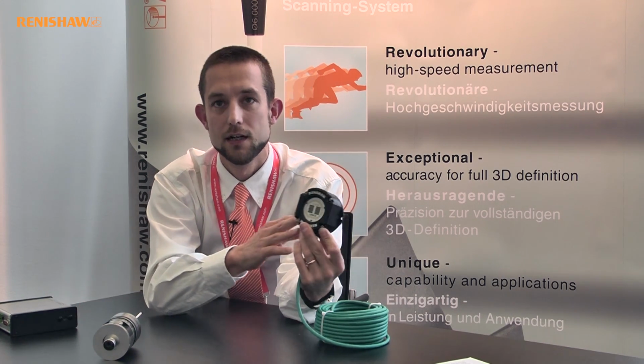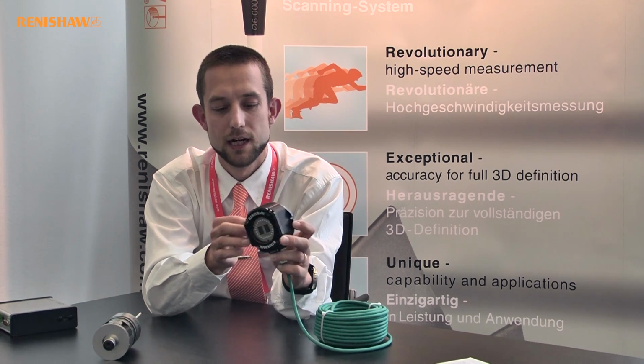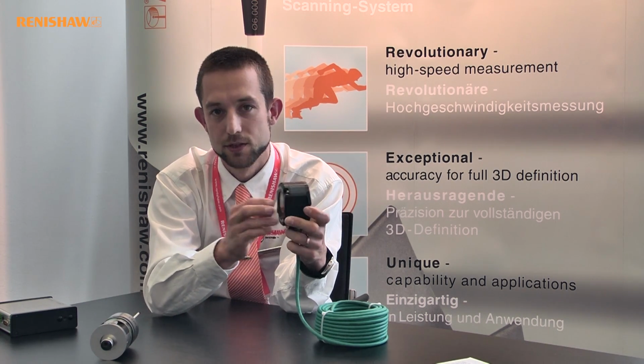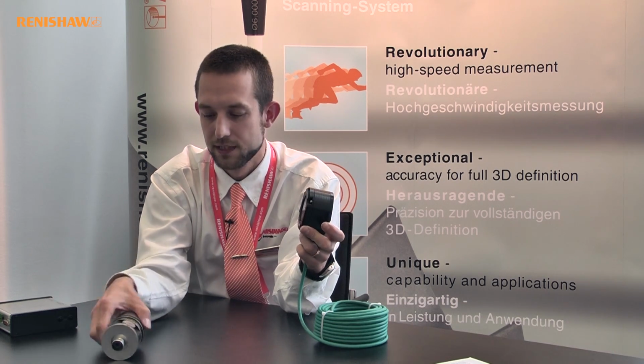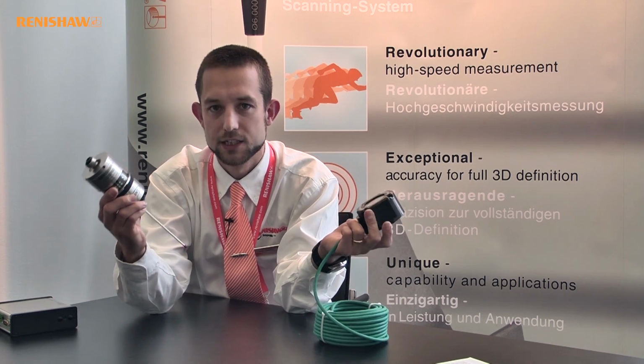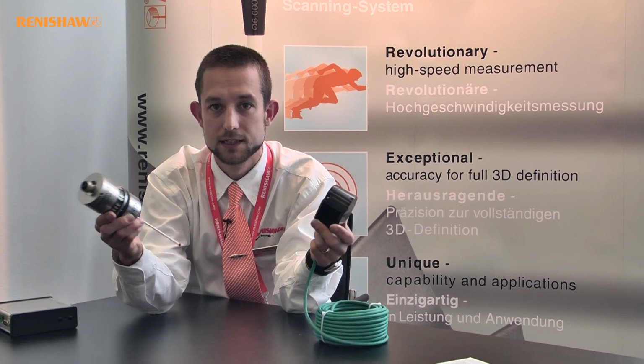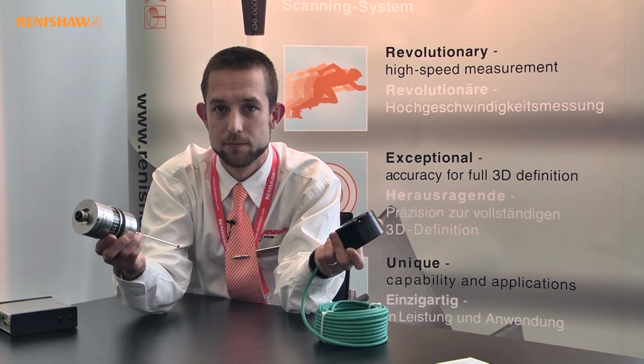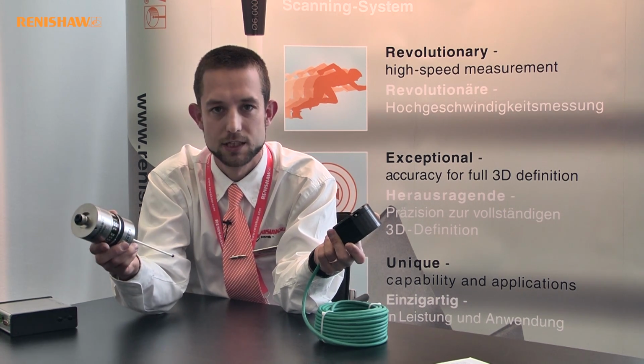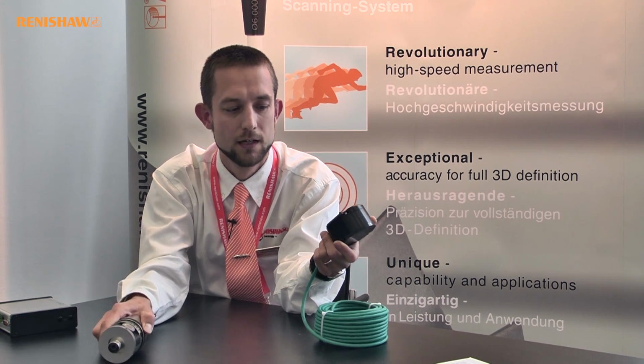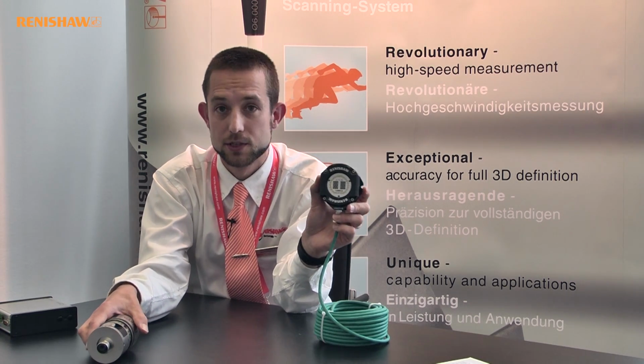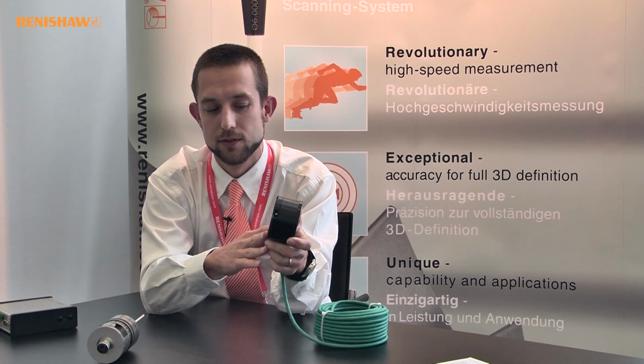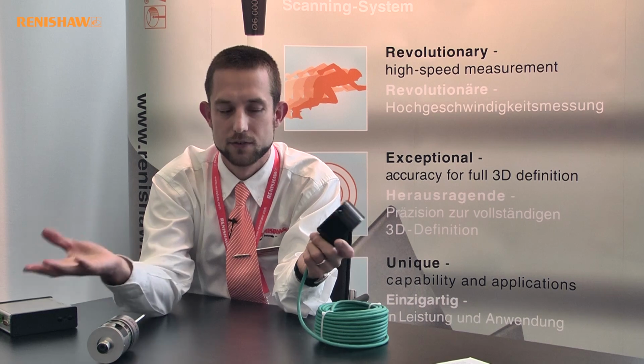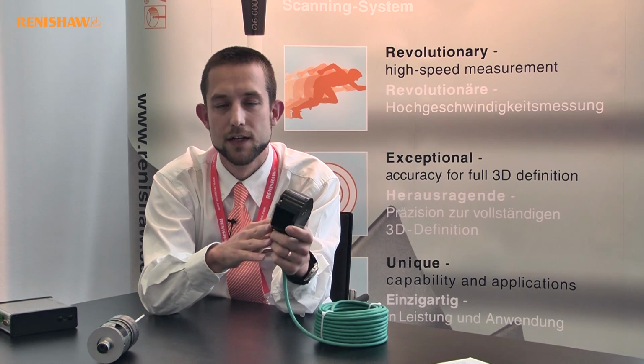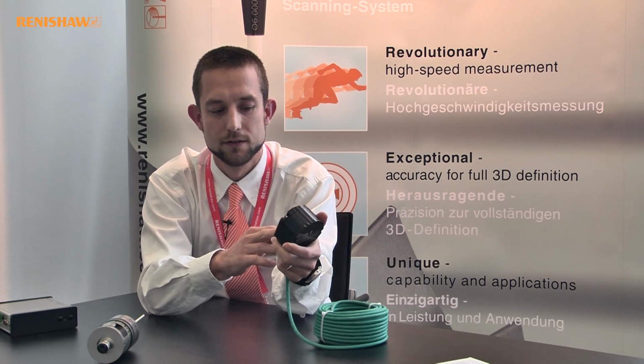So this is the OMMS. As with a normal Renishaw system, this is mounted on the wall of the machine, and it's communicating via infrared with the OSP60. It's actually bidirectional communication because, as we'll discover, timing is very important when you're trying to synchronize measurement data with the Sprint system. So the OMMS, you can have up to 2 of these in your machine. So if you've got a large machine, or if it's, for example, a tilting head type, then you can use 2 of these to ensure that you've got line of sight.